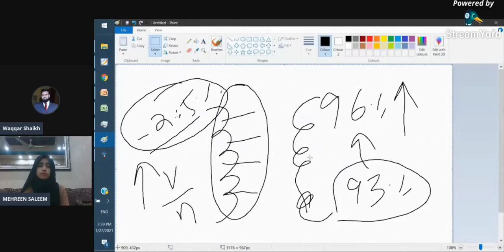To keep it simple, there are three important cable parameters to take from the manufacturer's database. Any cable, whether 3-core or single core, has a resistance value and an inductance value, both given in ohms per kilometer. Sometimes the inductance is given in millihenries or henries, and then you can use 2 pi f L to convert it into ohms. These are the two most important values of a cable.